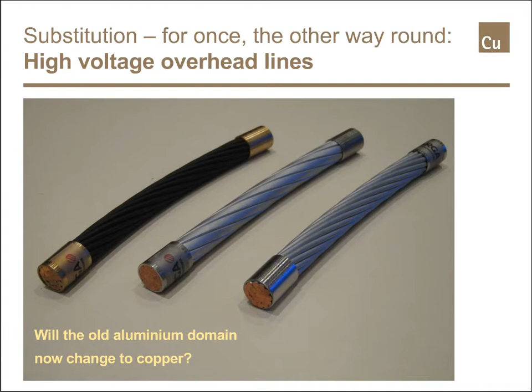Now, it is not normally that we produce higher losses, but in those situations where such a high load, a peak load, occurs only 100 hours a year or so, the copper conductor is really a solution where an extra line cannot be installed.